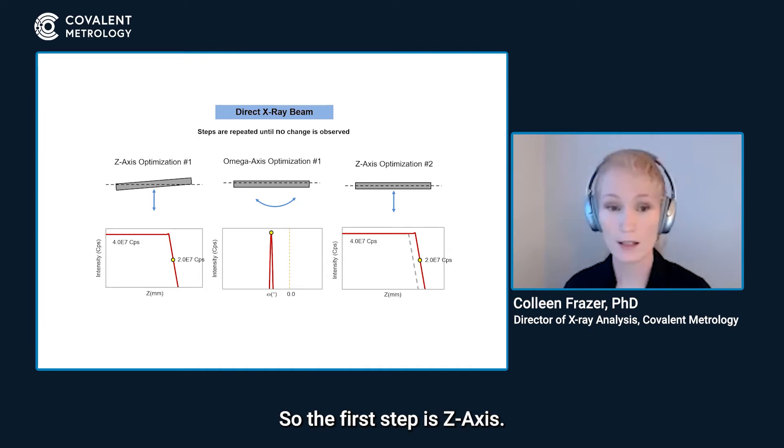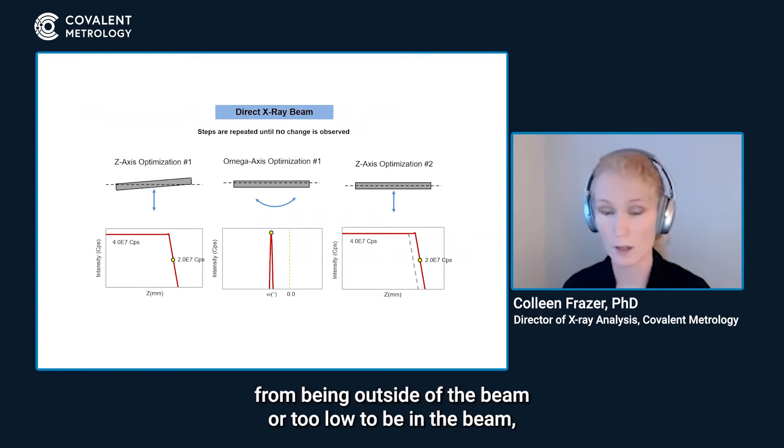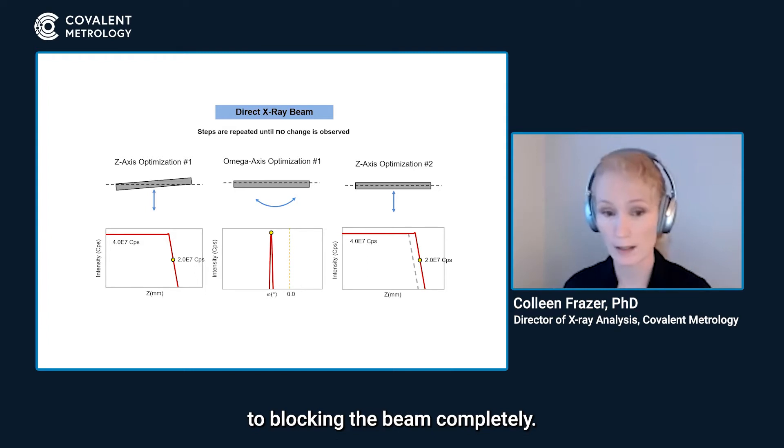The first step is Z-axis. If you're familiar with the diffractometer, the Z-axis is the height of the sample in the beam. We're bringing the sample up from being outside of the beam or too low to be in the beam to blocking the beam completely. The plot of that is on the lower left.